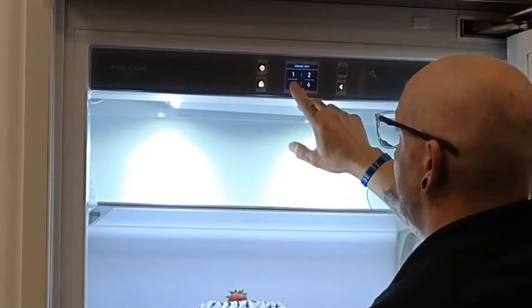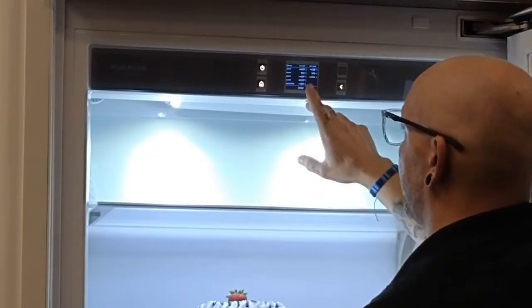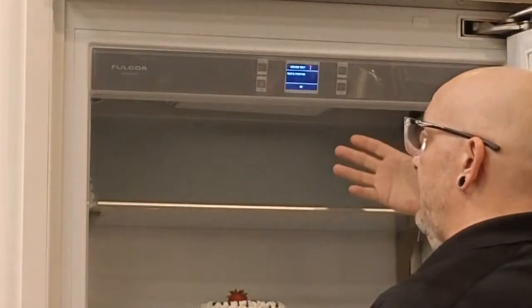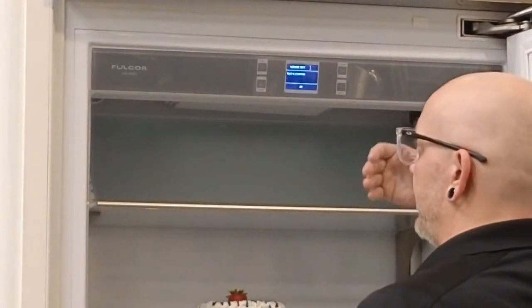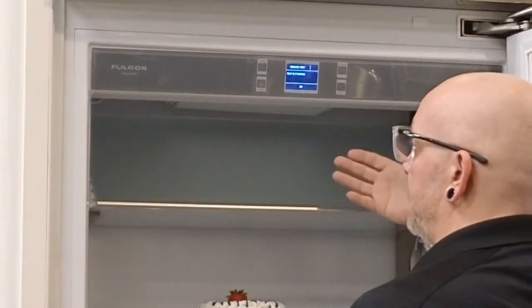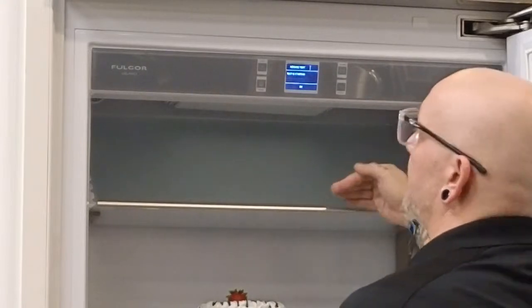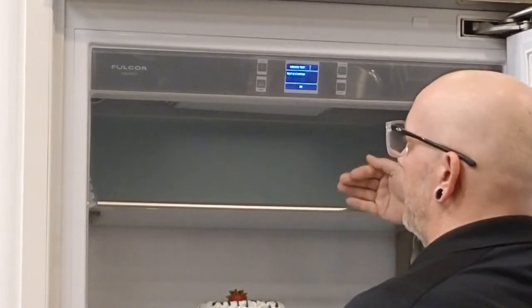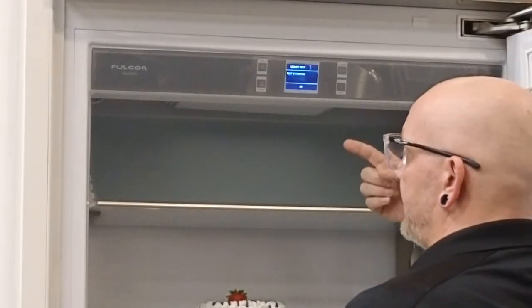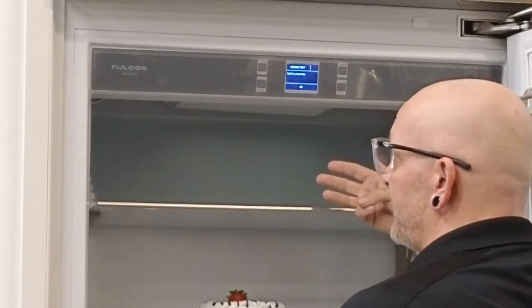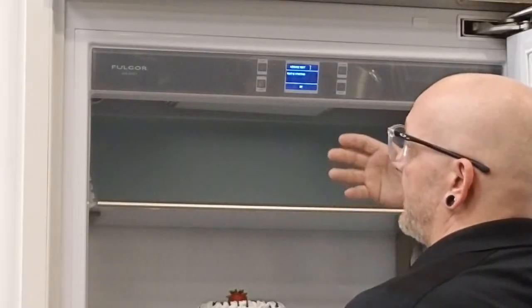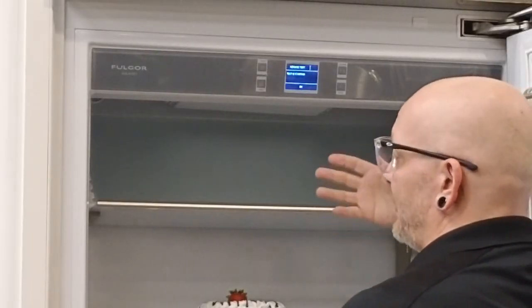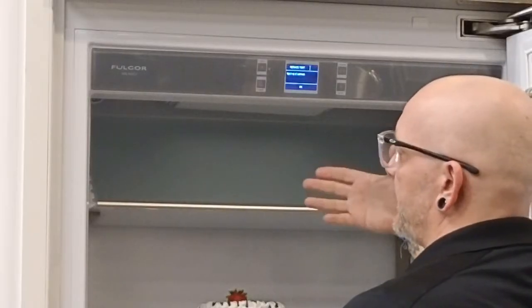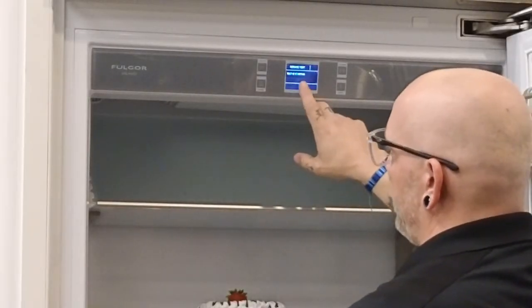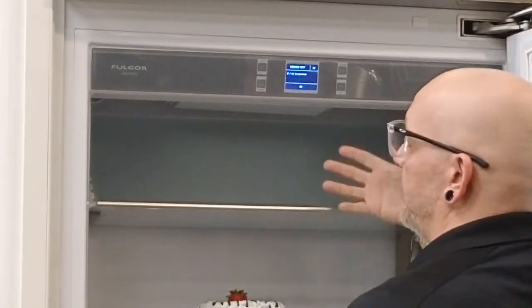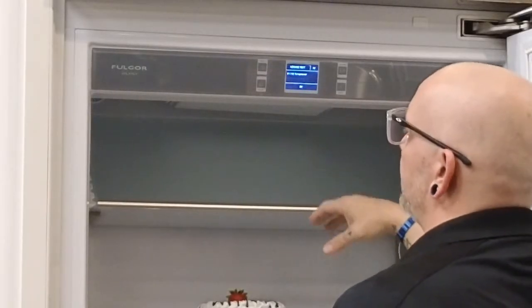First thing again, you're going to see is your temp probe readout, but we're going to push enter. Now, there's only a few tests that I would personally go into service test for because there are so many steps and it is a very linear service mode. You can't go backwards, you can only go forwards. So I would go in here to test compressors, fans, heaters, because as I scroll through, you'll see things like RGB lighting and things like glass door that are just legacy features on previous models and generations. So you maybe end up pushing the OK button more than you would actually be doing any kind of testing. So just be mindful of that.